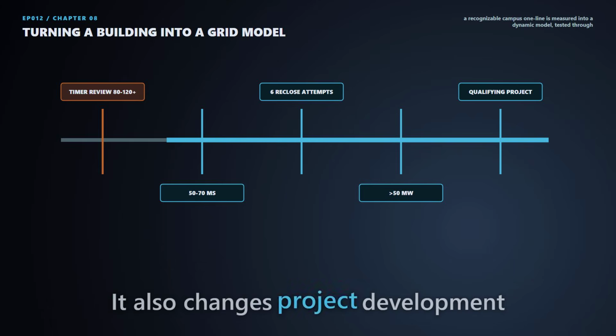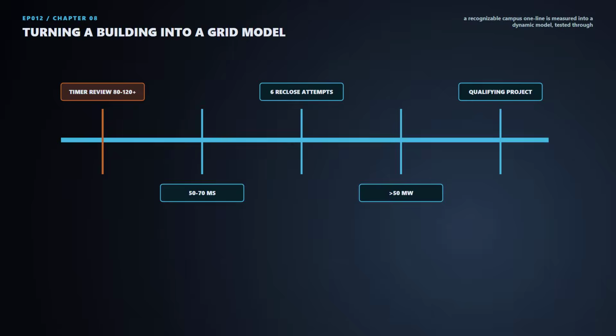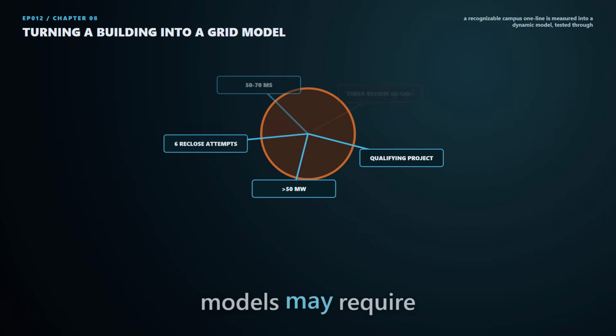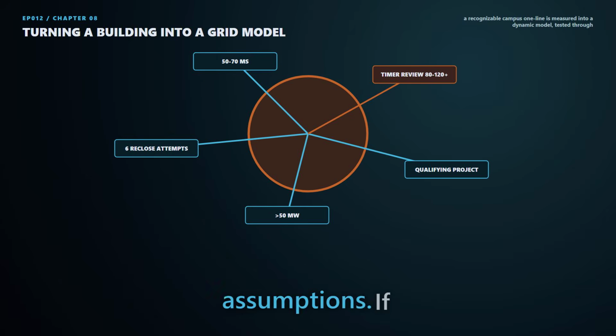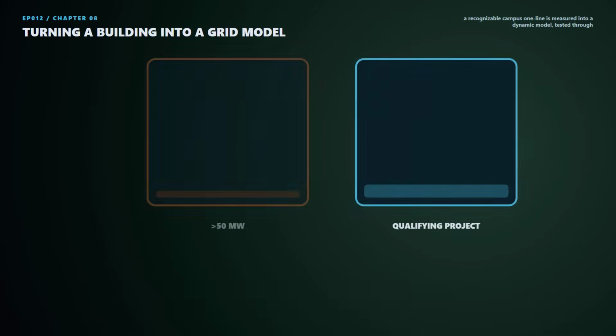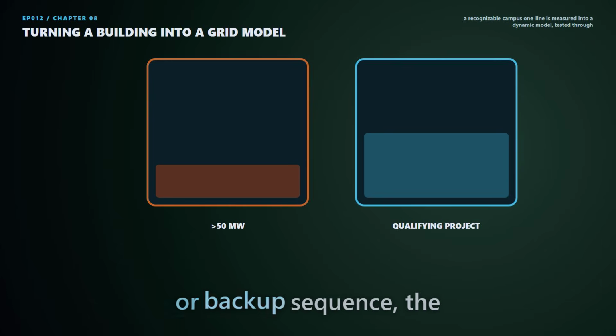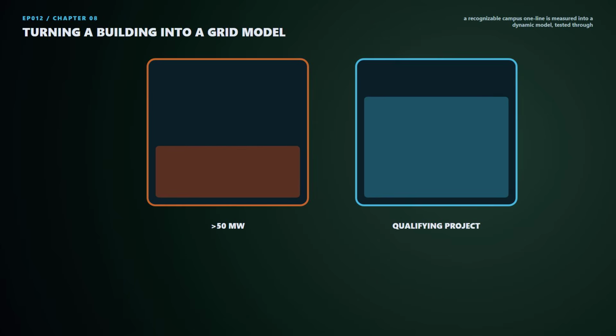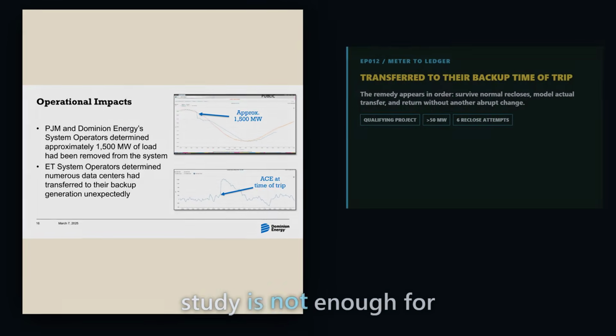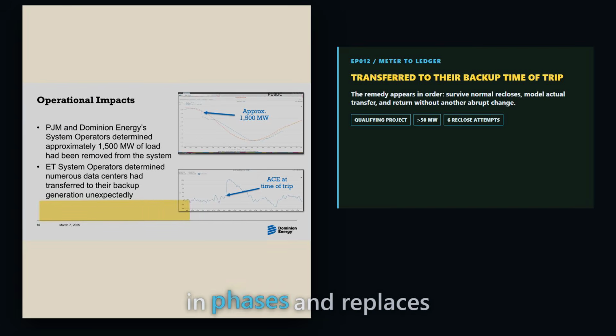It also changes project development long before a building opens. Missing or incomplete dynamic models may require additional study or conservative assumptions. If later equipment changes alter the UPS, protection, or backup sequence, the model has to change too. A one-time interconnection study is not enough for a facility that expands in phases and replaces electrical equipment over decades.